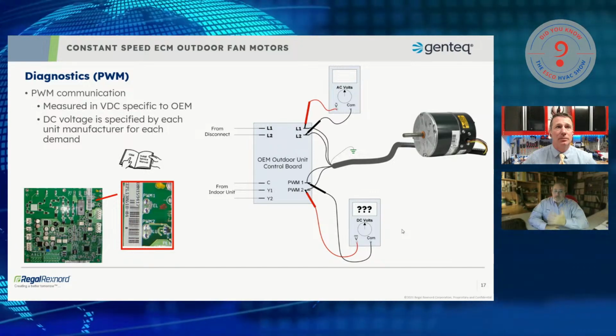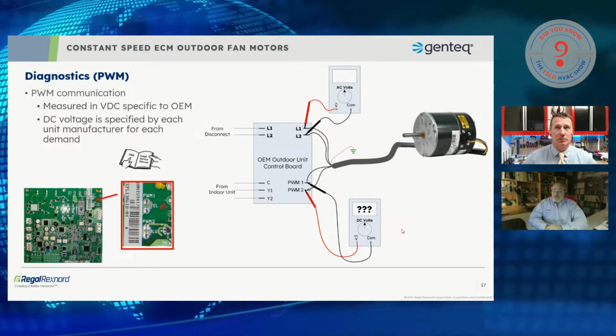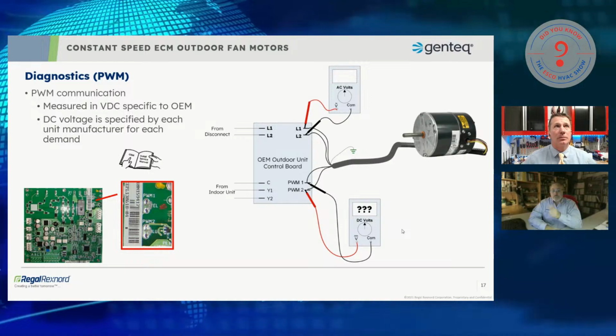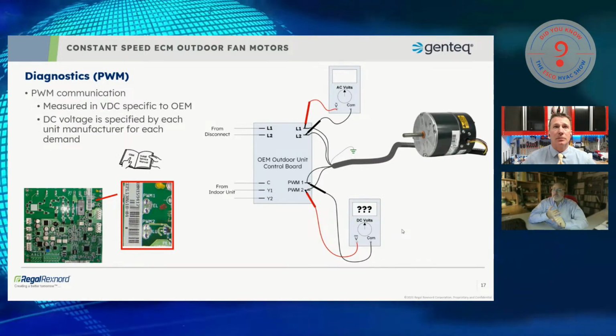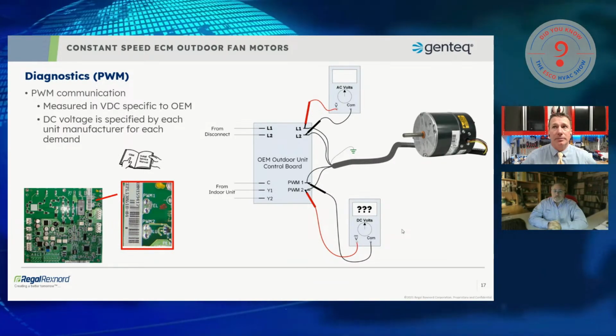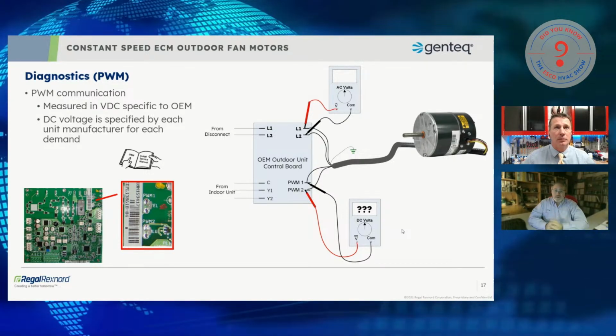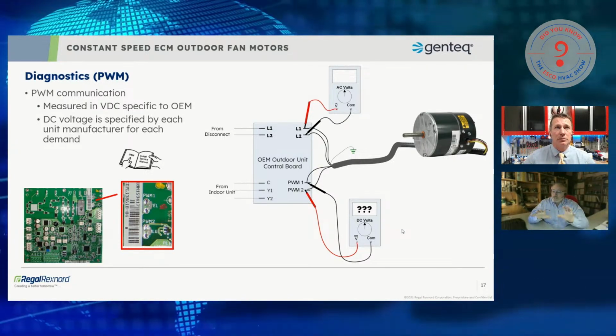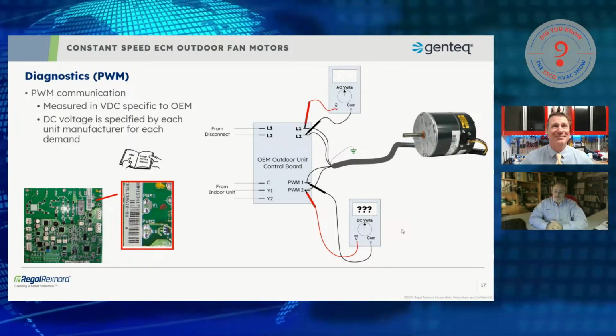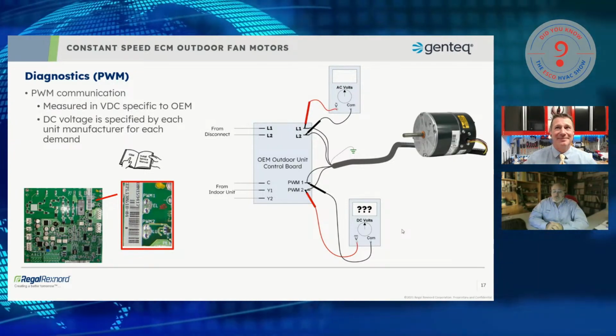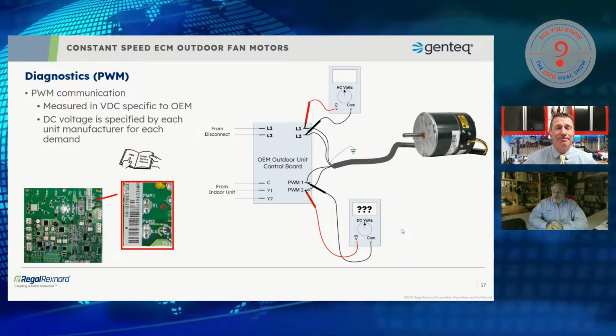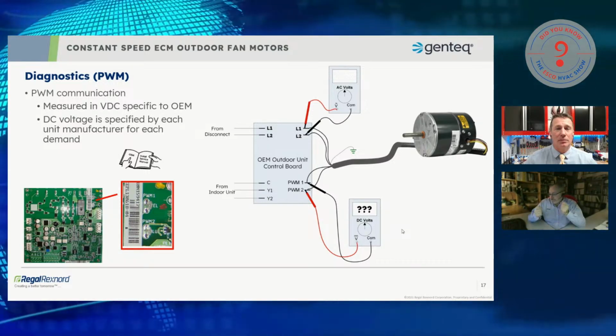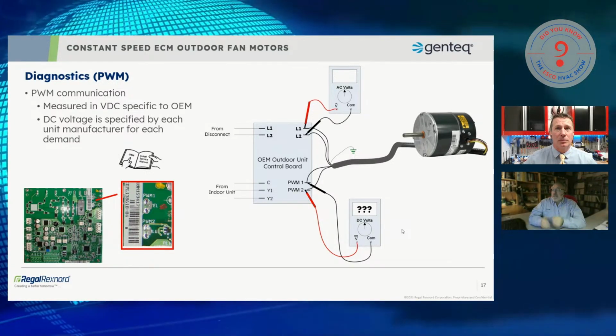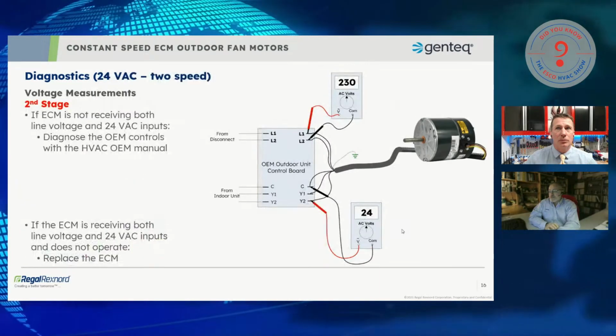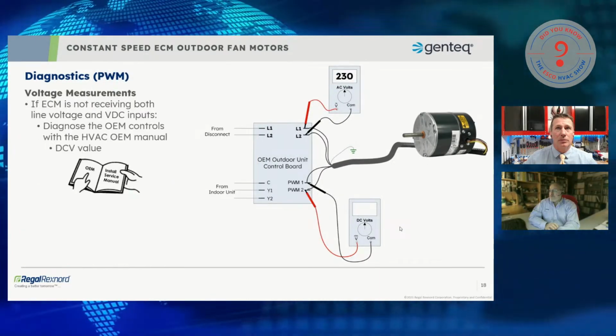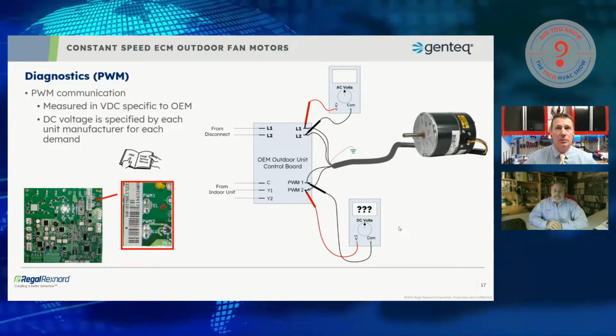So this signal really is dependent on you getting that OEM manual out, finding that diagram or chart or paragraph that says stage 1, you should see 2.2 volts DC. Stage 2, you should see 3.5 volts DC. Again, those were examples. Don't write those down. And then simply applying your meter to those PWM 1 and 2 pins and measuring that DC voltage. So whatever that value is, let's say it's 2.5. I put my meter on there. I have 230 volts and I have my correct DC voltage.